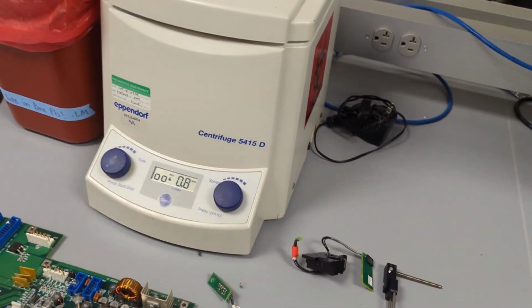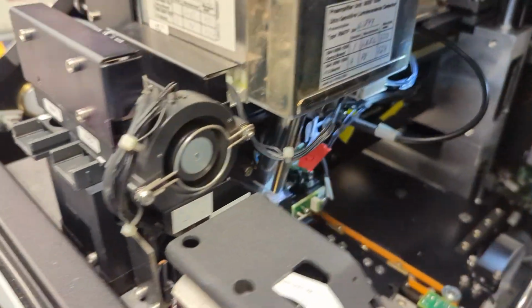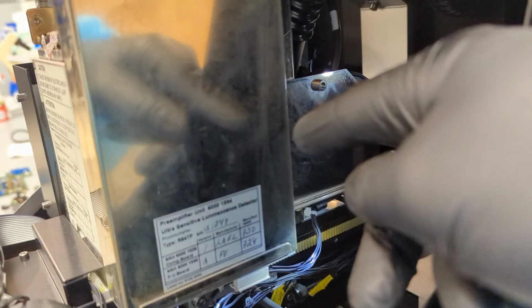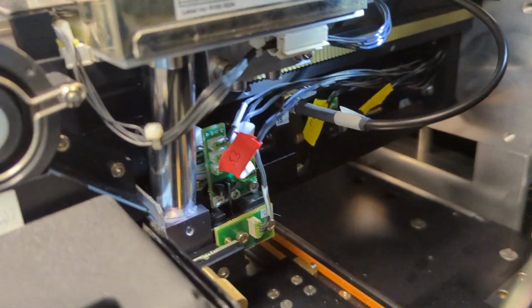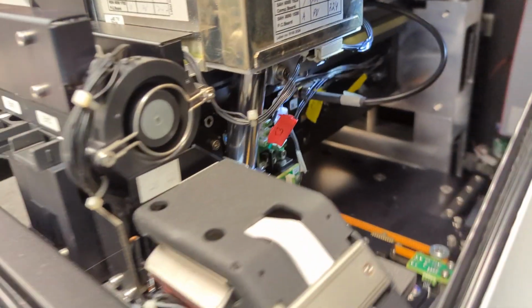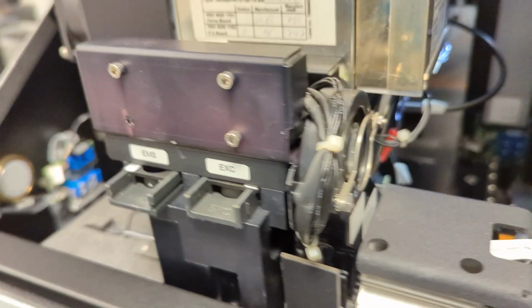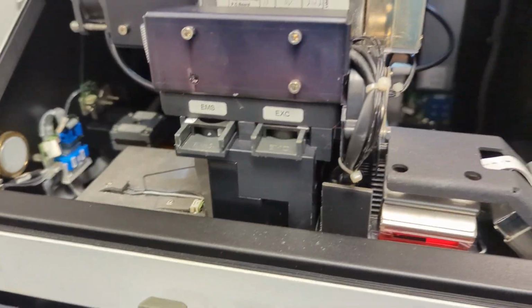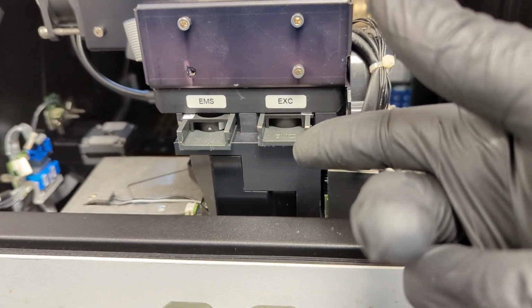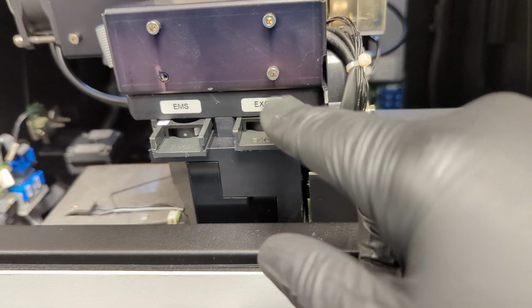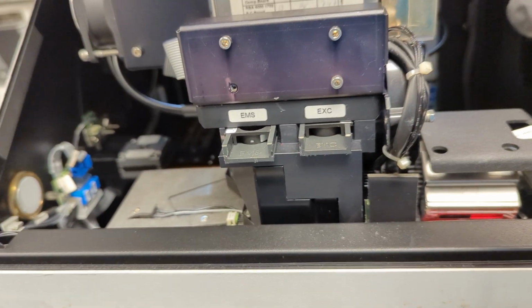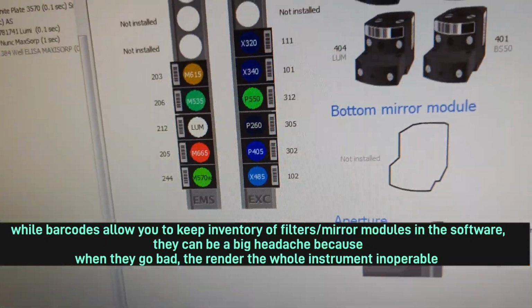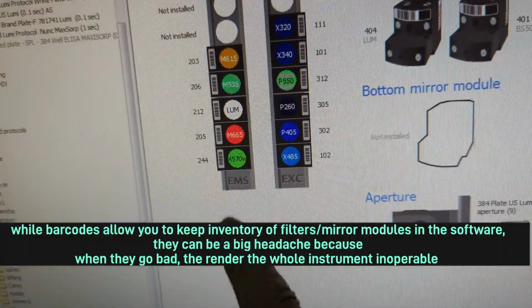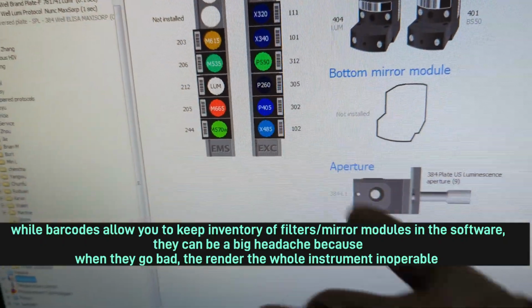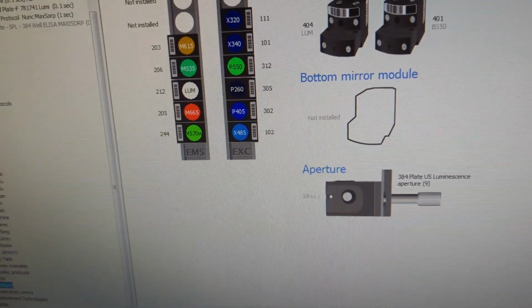So moving on, one thing, speaking of absorbance, and we'll get to this as well, so in between the lamp, the excitation lamp back there, and the excitation light selector, you have some excitation filters. What's interesting about this instrument, at least in its current configuration, is it doesn't have a monochromator. So instead, you've got all these filters that you can choose from that come out on this rail, and they're barcoded so the instrument knows which kinds are in it. So for example, you've got these all loaded currently in there, and there's also emission filters as well, which we'll get to in a second, but these are in between the flash lamp and the excitation light selector.